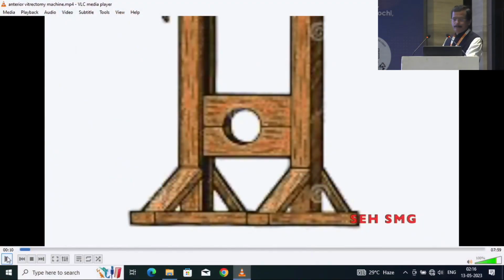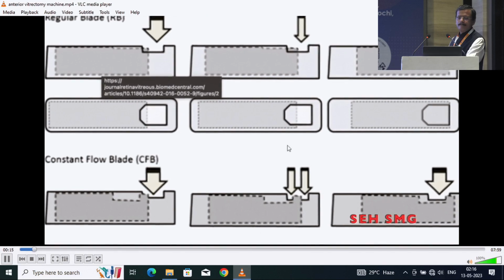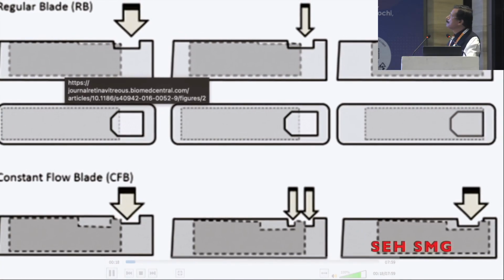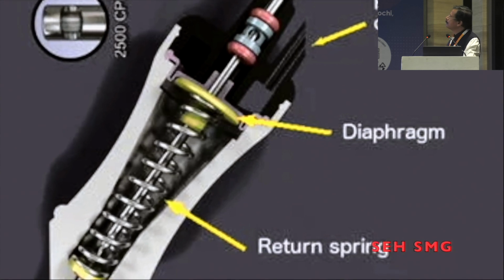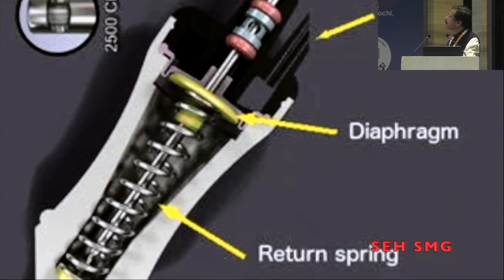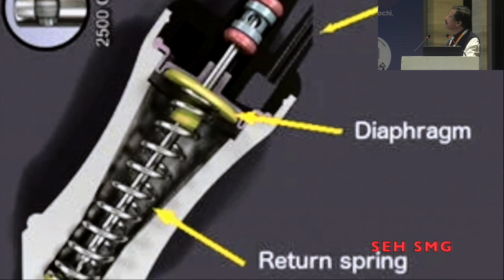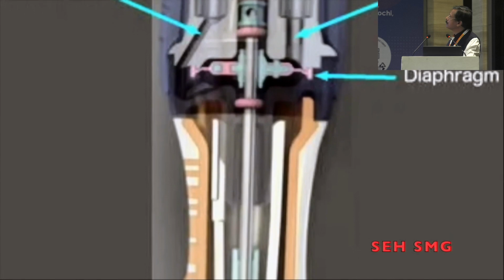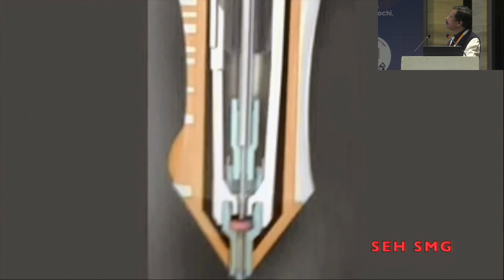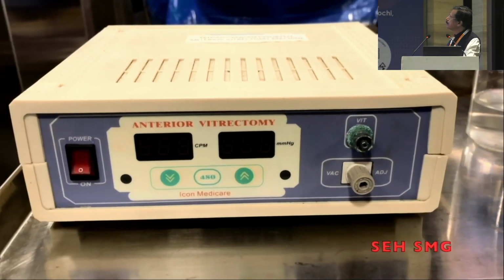Yeah. Vitreous cutters are based on the guillotine principle. This is not changed. When the vitreous gets engaged to the cutter, it gets cut into small pieces and makes aspiration easy. When you see inside, there is a spring which will be moved with the help of air pulse, and the blade will move to and fro. There are modifications of these cutters also where there is no spring, but there is the air pulse for the forward movement and backward movement of the cutter.